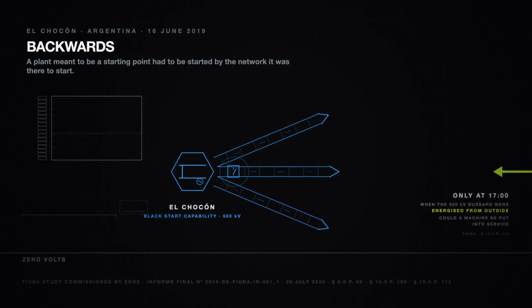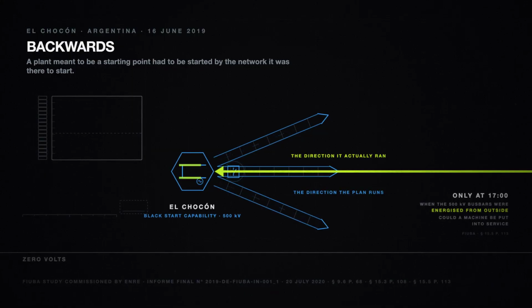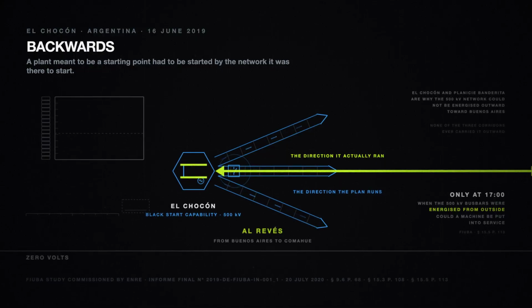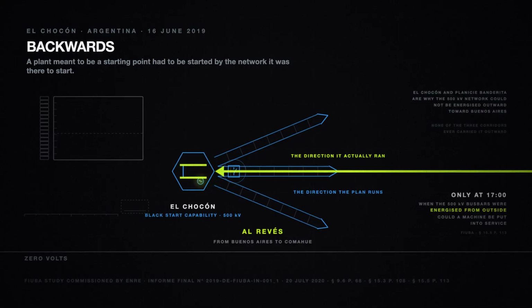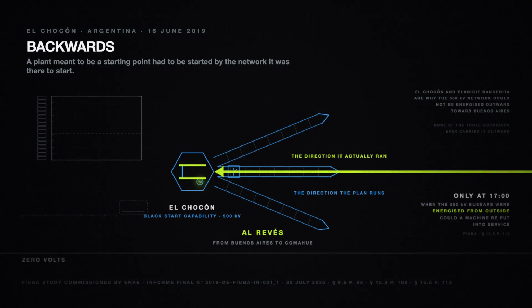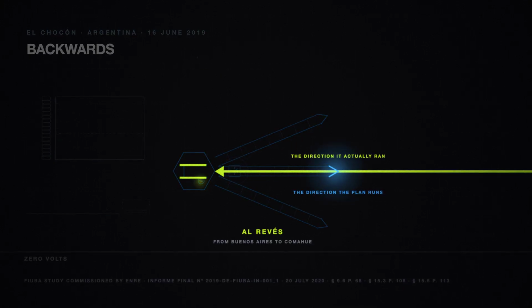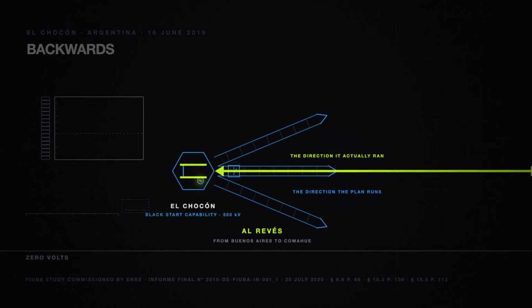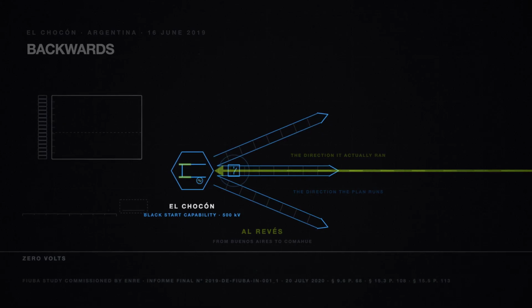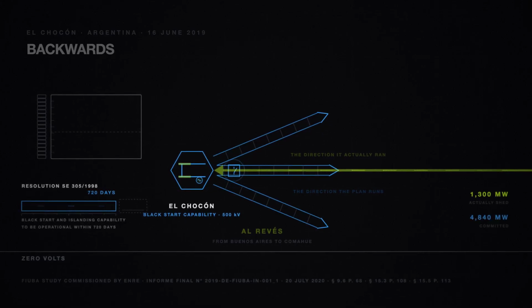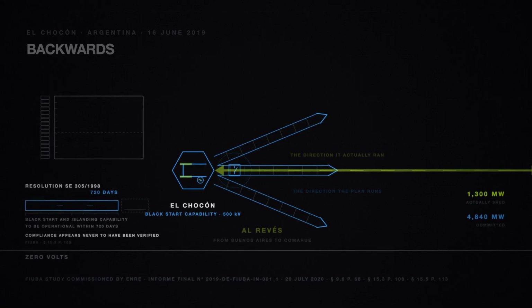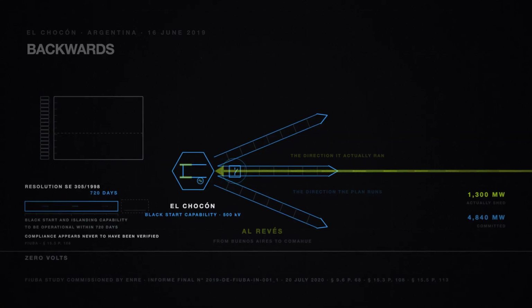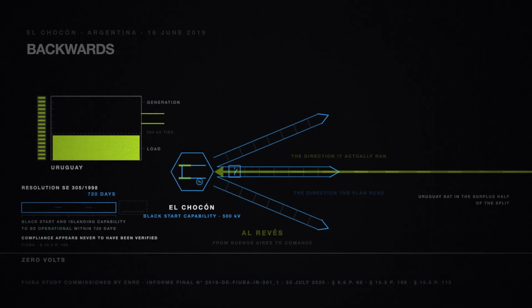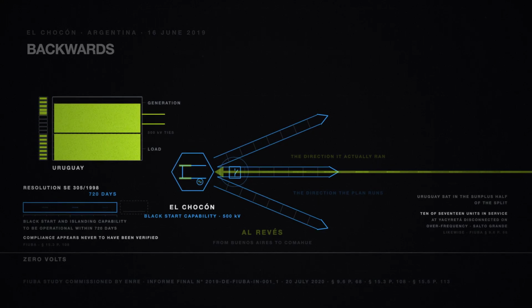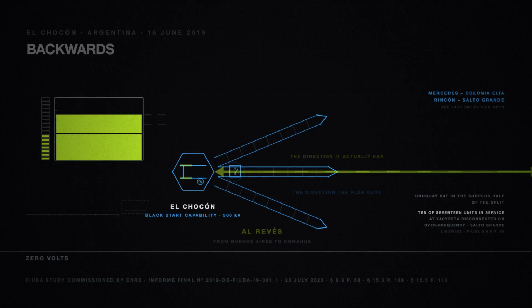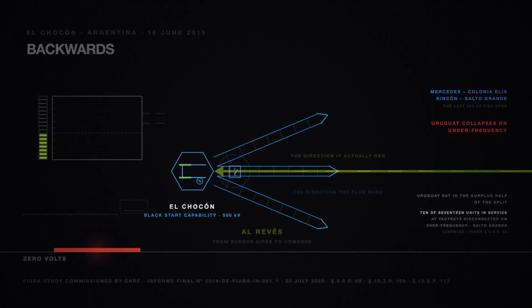Energized from outside. A plant meant to be a starting point had to be started by the network it was there to start. The study concludes that El Chocón and Planicie Banderita are why the 500 kilovolt network could not be energized outward toward Buenos Aires. It had to be done, in the report's words, al revés, backwards, from Buenos Aires to Comahue. A footnote: a national resolution of 1998 required black start and islanding capability within 720 days. Compliance appears never to have been verified, and Uruguay was not simply dragged down alongside Argentina. It sat in the surplus half of the split, tripping on overfrequency, and collapsed on underfrequency only when the last ties opened.